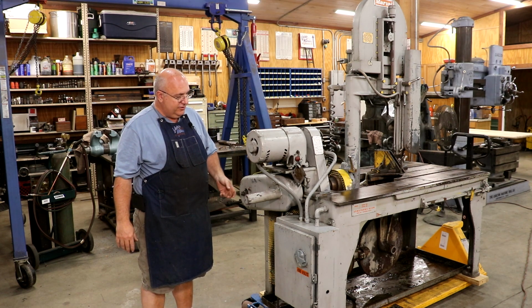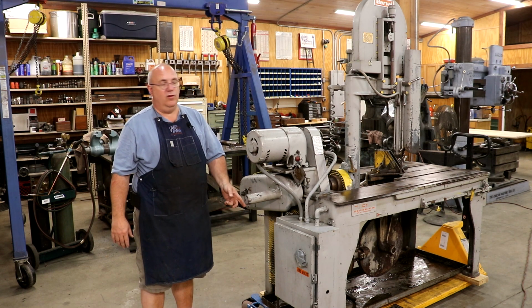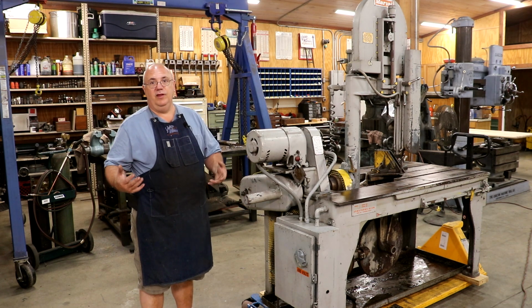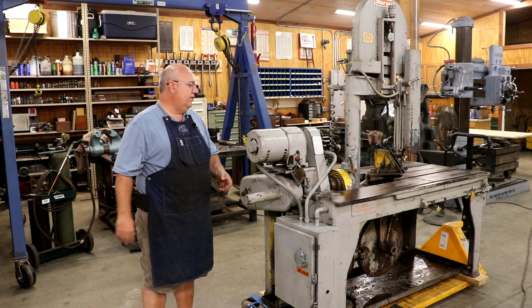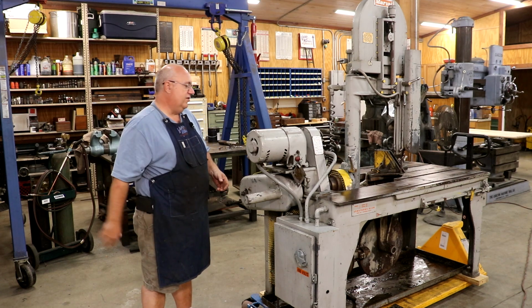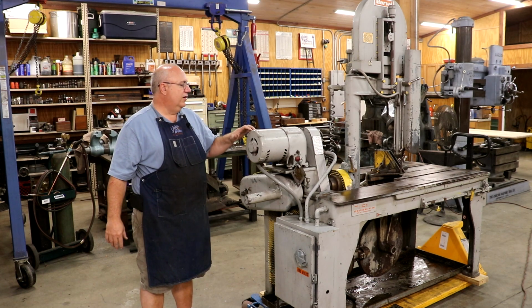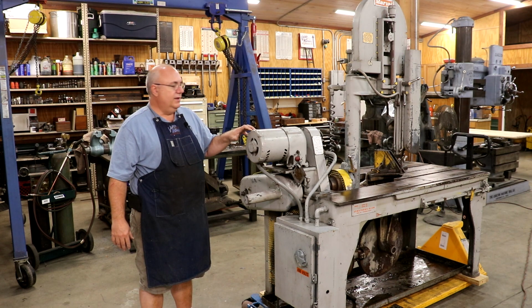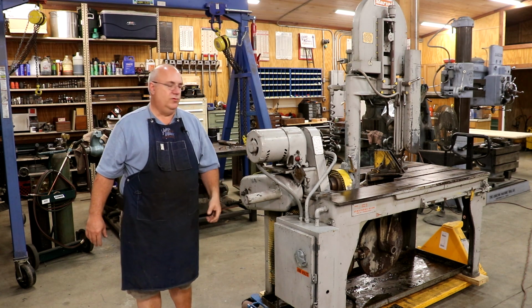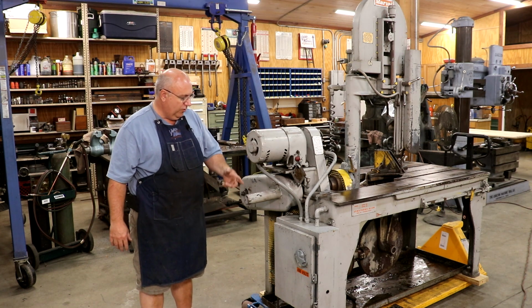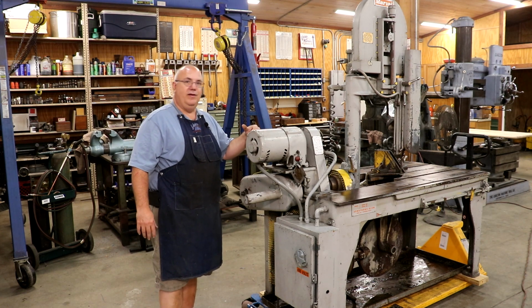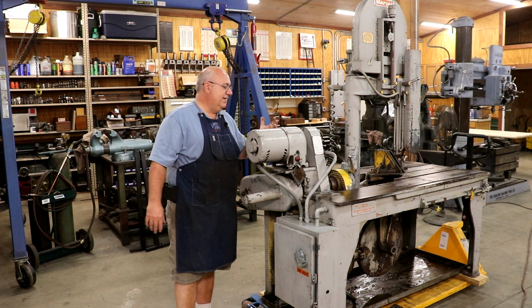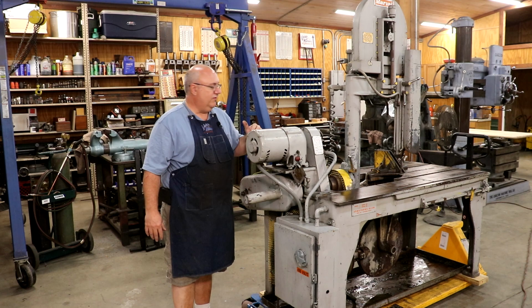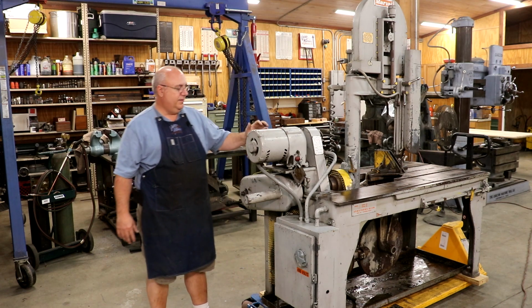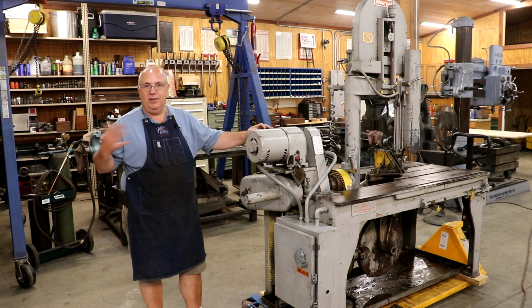And now most factories are set up to run on 480 volts. The advantage of running on 480 volts is basically you can run smaller wires to your machine. The motor's going to pull less amps than if you run on the lower voltage, 220 or 240 volts, whatever it is. My shop is set up on low voltage, on 220 volts. I don't have 480 coming into the shop.